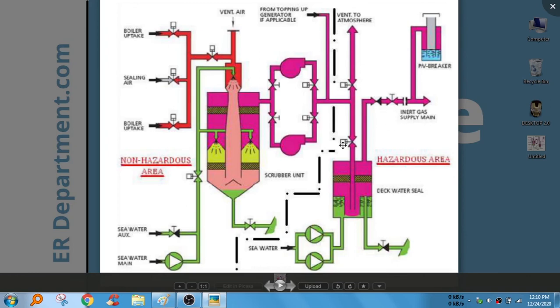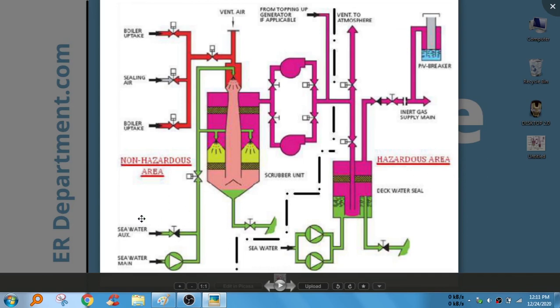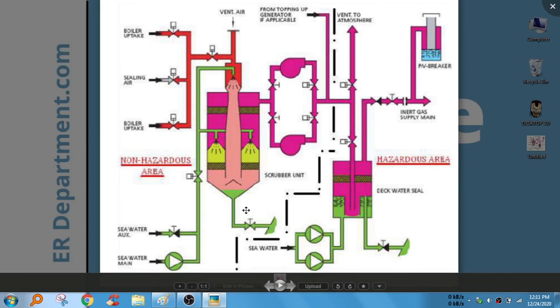And then I have got an extra point which says, as you can see here, this is inert gas system. In this, water is given overboard directly. In case of inert gas generator unit where we are firing diesel and making exhaust gases, in that system, in case of flame failure, the water is transferred to the bilge holding tank. I think it's because if there is a flame failure then the oil or the diesel may be dripping. The diesel should not go to overboard, I think that's the reason.